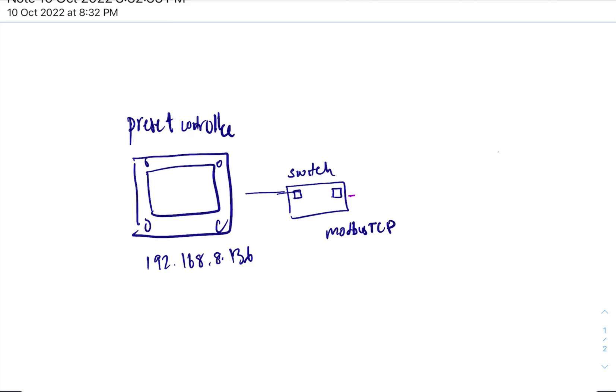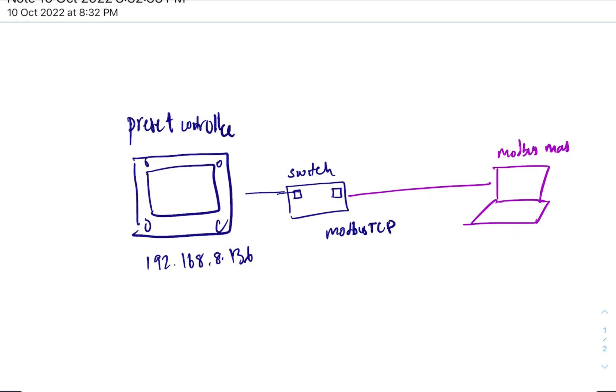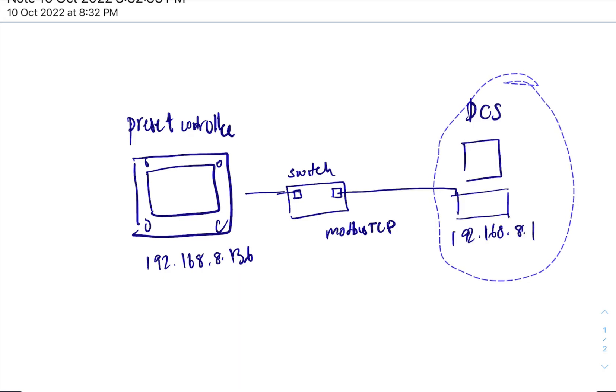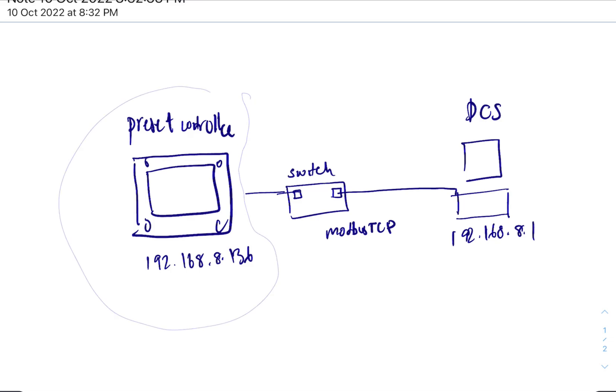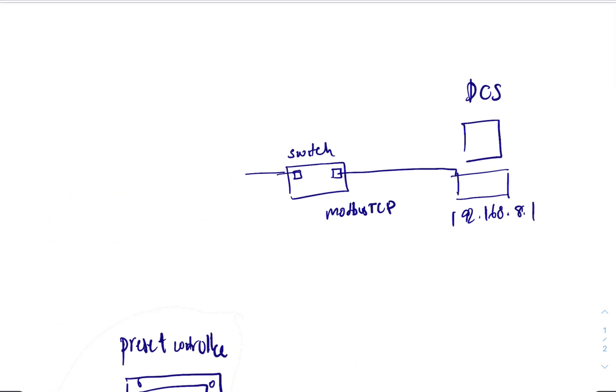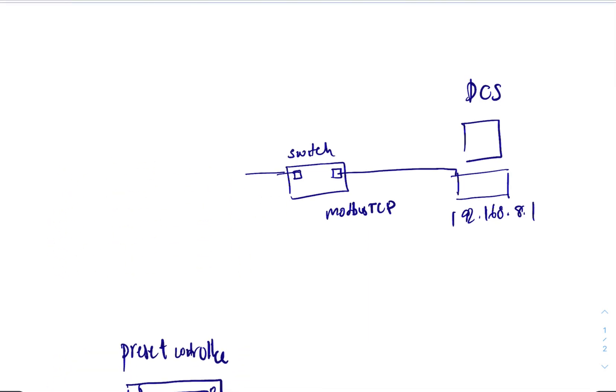And you would put it where the slave is in this section. So let's put back the DCS. And if you suspect the preset controller has a problem, you would take the preset controller away, and then again you would put your laptop here. And what would you do? You would run modbus slave.